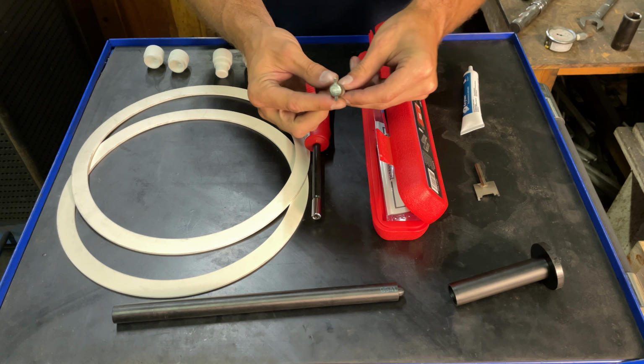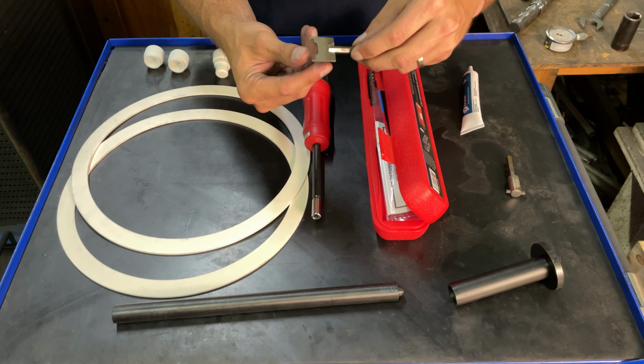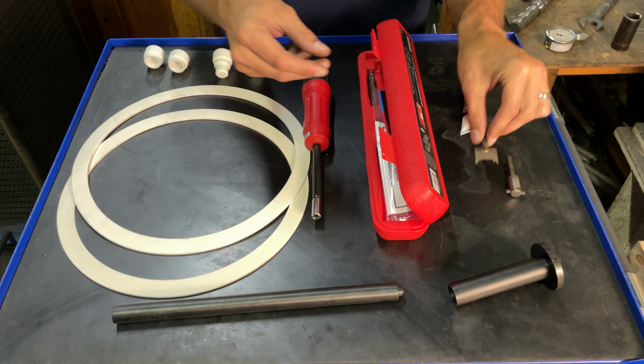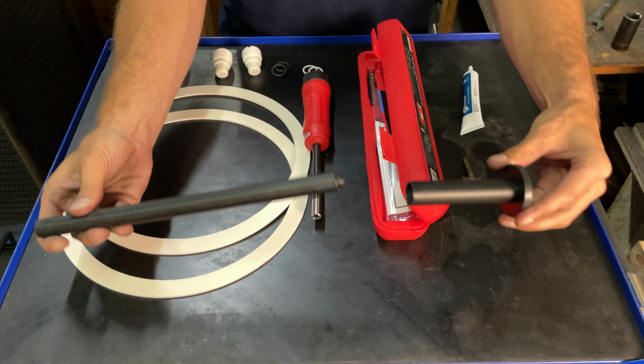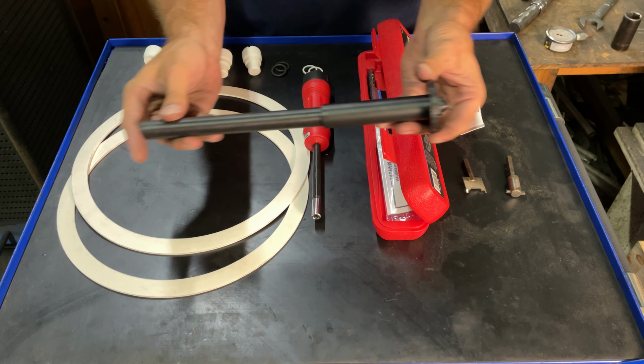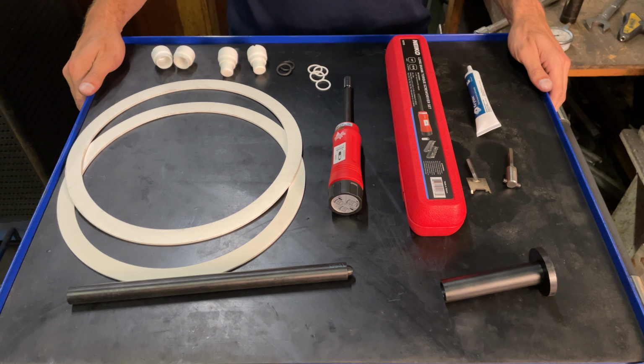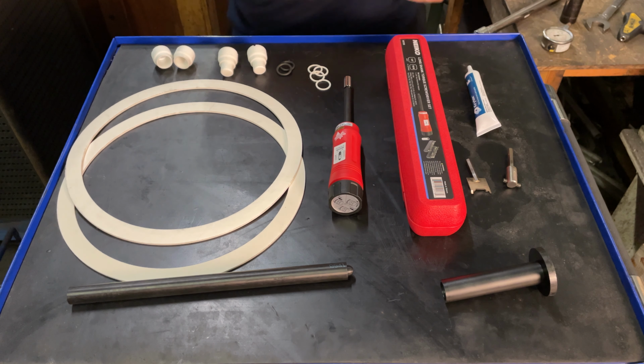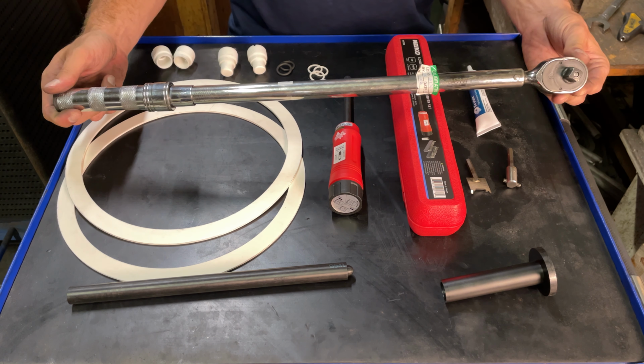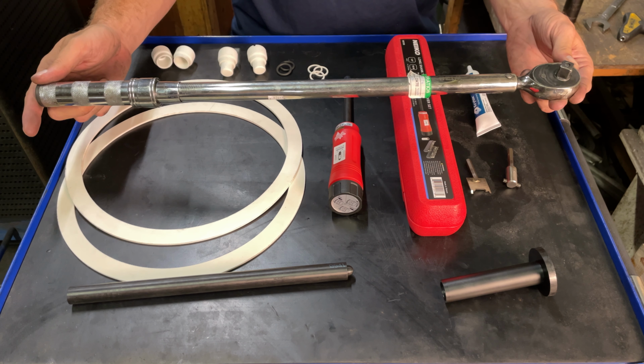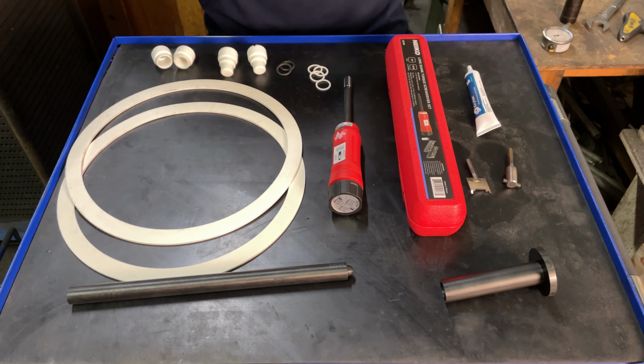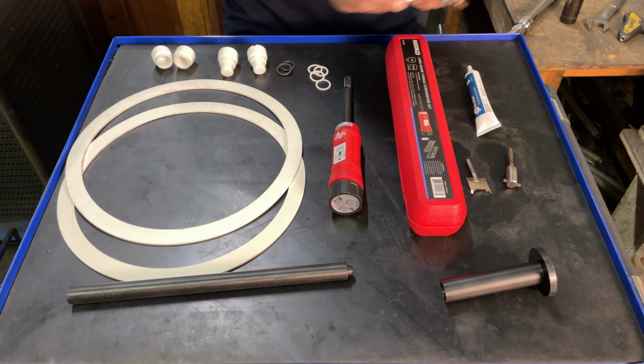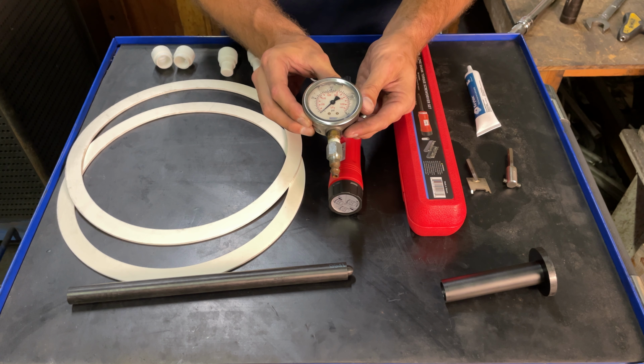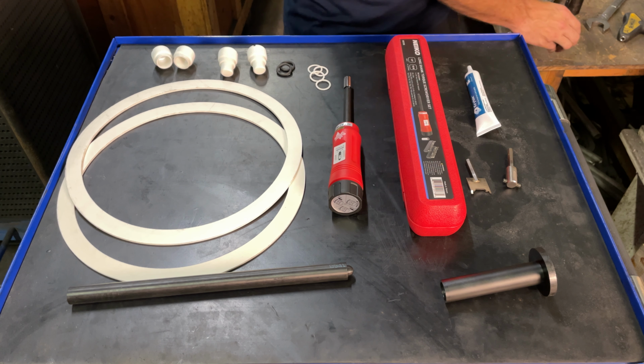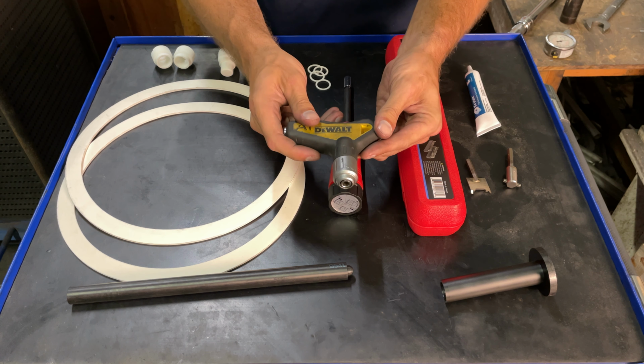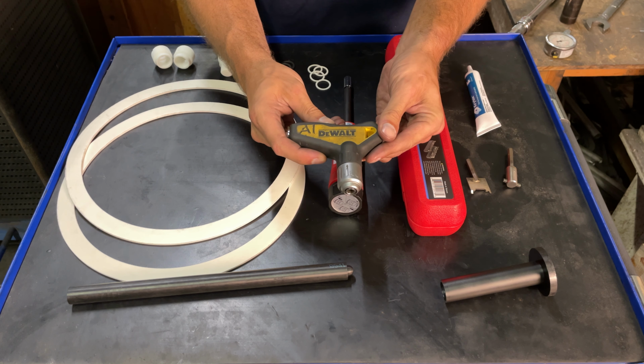The tube nut bit, the tube nut removal tool, and finally the ring positioning tool. There are a few additional tools not included in your box kit that will be helpful during this process. A socket wrench or equivalent for removing the clamp plates to adjust the tube sheet, a gauge for hydrostatic testing, and a ratcheting T-handle to remove the tube nuts.